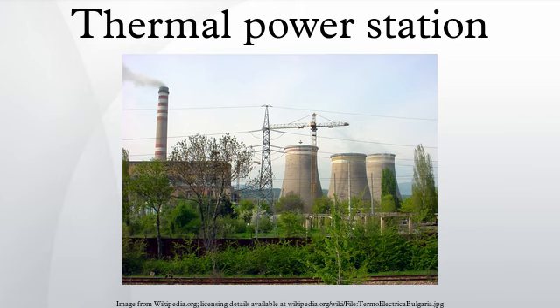The United States also requires the height of a flue gas stack to comply with what is known as the Good Engineering Practice stack height. In the case of existing flue gas stacks that exceed the GEP stack height, any air pollution dispersion modeling studies for such stacks must use the GEP stack height rather than the actual stack height.